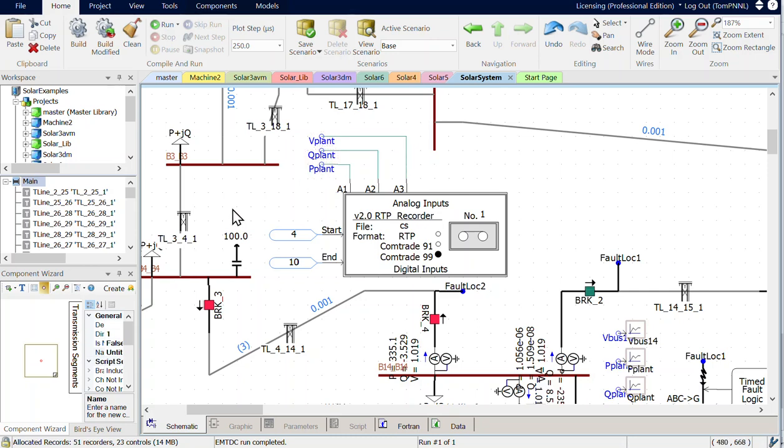There are synchronous machines and other elements in the system, so we want to look at those as well. I'm not showing that here, but you of course want to look at other machine angles and see if any of them are losing stability. Doesn't appear to be the case in this simulation. When I run that study script, it's going to run those 9 simulations in sequence.